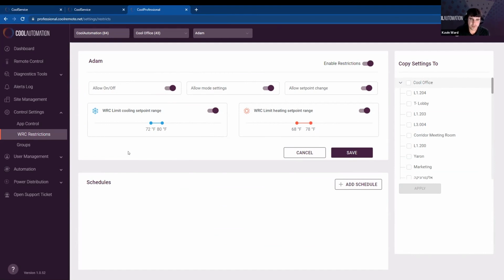If any changes are made at the wired or the local level from the wired remote controller, our software will actually restrict it back to 72, or if it's above 80, it will bring it back to 80 as well. It will not allow for the actual person on site to turn that unit off from the controller. If these are selected, you cannot change the mode, or you can completely limit any set point change from the local level using this option here. This can be scheduled as well, but ultimately these set point restrictions will give you more control of your space, optimizing efficiency, allowing your system to be satisfied and more comfortable overall.